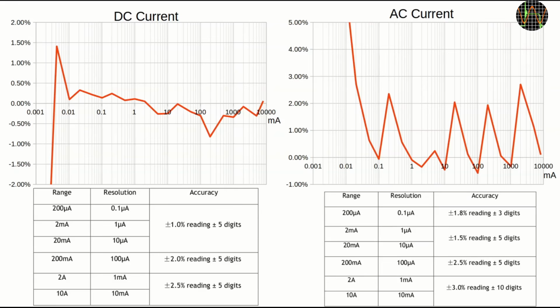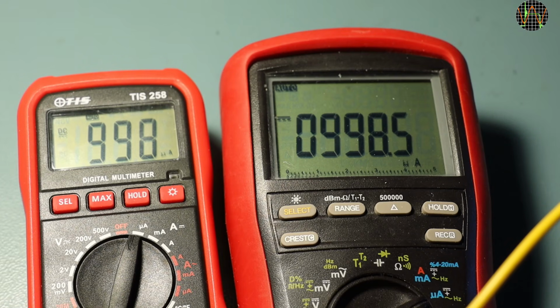Moving on to current. DC again on the left and AC on the right. In both cases the horizontal axis is milliamp, not amps. It is a very similar picture. DC current is quite accurate once you go above 10 microamps, much better than the specs. For AC current, we have again the prominent error spikes caused by switching ranges and low accuracy at the beginning of a range. As with AC volts, you need to consider the ± digit part, and then everything is still in spec. Once you are above the beginning of a range, AC currents, similar to AC volts, are actually quite accurate. As I said earlier, current measurements on the TIS-258 work in a mix of manual and auto ranging.